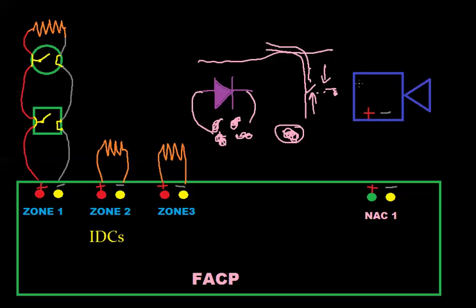Internally in all of these horn strobes, there's a diode. When we go and complete the circuit positive to positive and negative to negative, what's actually happening, if you were to meter this right now on most panels, this would actually be negative. Even though it's labeled positive, the polarities are shown in an activated state. In a normal condition, the polarity is going to be reversed. If you put your meter on voltage on these two terminals, you would read a negative 24 volts. Most modern panels actually jump that down to a smaller voltage, but let's just say that's a negative 24 volts right now.